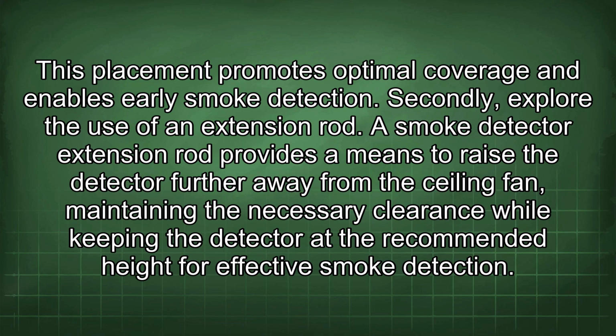Secondly, explore the use of an extension rod. A smoke detector extension rod provides a means to raise the detector further away from the ceiling fan, maintaining the necessary clearance while keeping the detector at the recommended height for effective smoke detection.